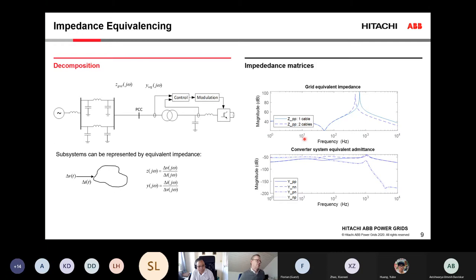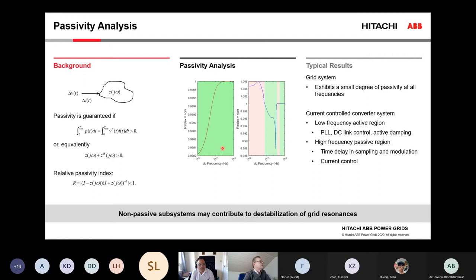For the converter system, it's a little bit more complicated because usually you have more or less the same behavior, at least in the passive components, in the positive and negative sequence. But we have a control system that introduces coupling between positive and negative sequence. So we need to represent this with a full impedance matrix with four elements: positive sequence, negative sequence, and the couplings in between. That could look like the figure here. And the first line of analysis that I find very, very useful is something we call passivity analysis. You can apply passivity analysis to either a grid system, for example.